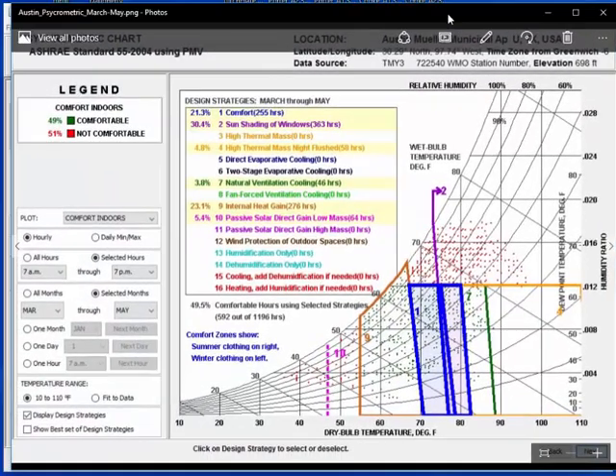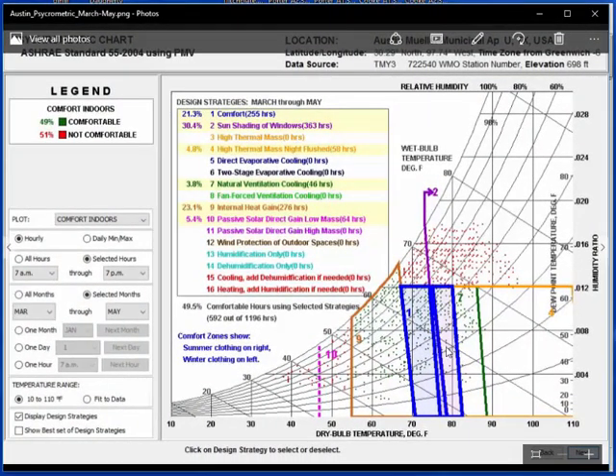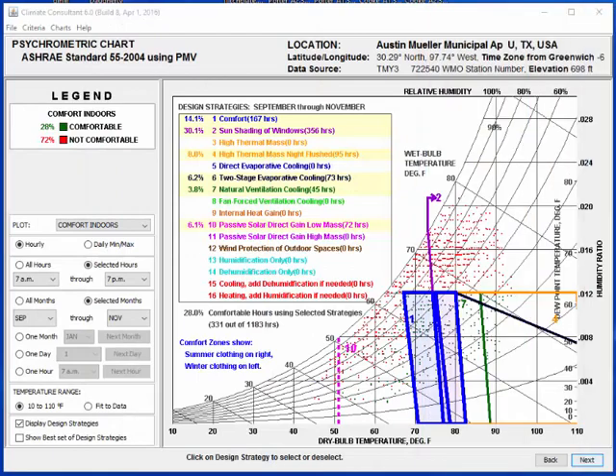Here's March and May. You can see once again high thermal mass with night flushing seems to work in March and May. So the two swing times of the year, that can be effective. In summer it's not very effective at all. Natural ventilation - same thing, once again in the swing months of fall and spring. Internal heat gain, because there's still some heating need, we can still use a little passive solar direct gain as well as internal heat gain.